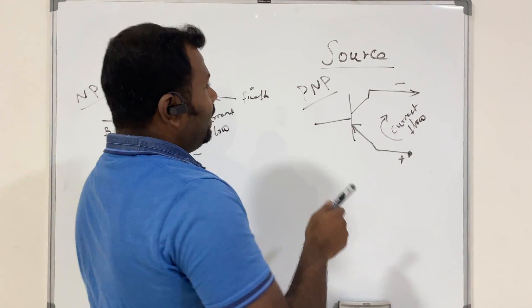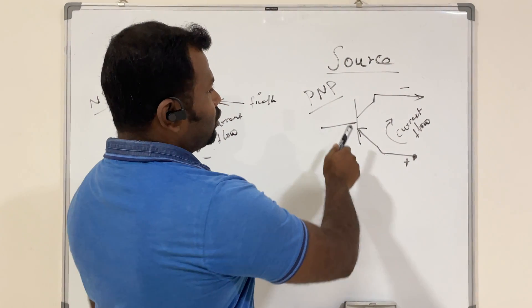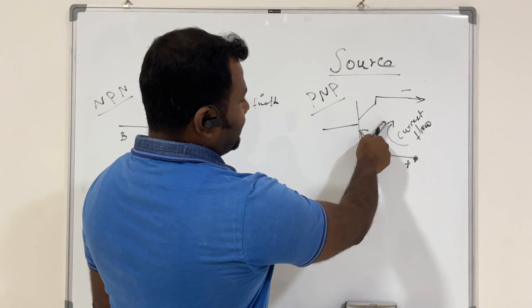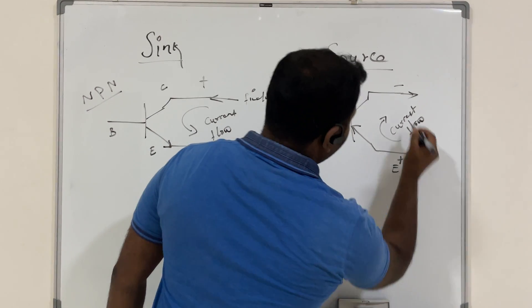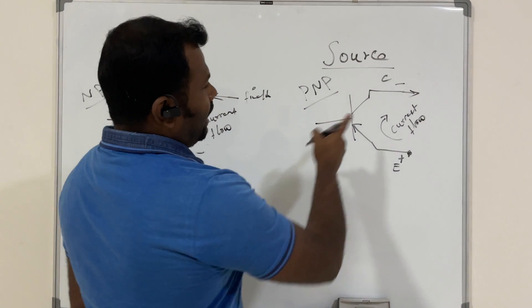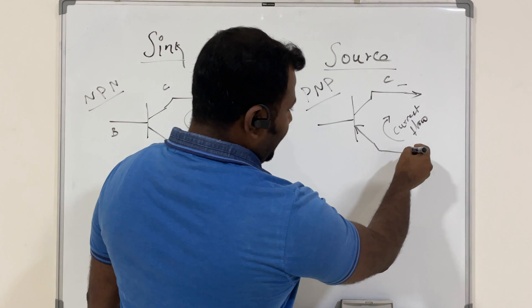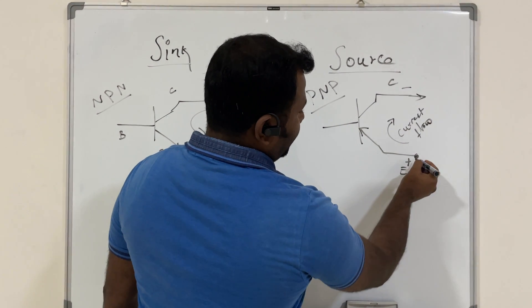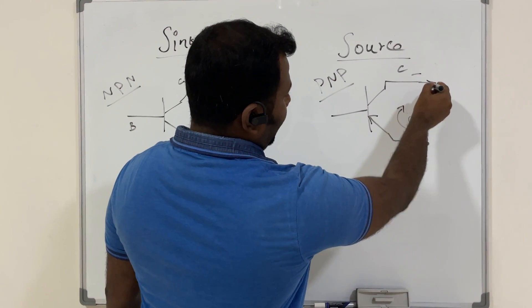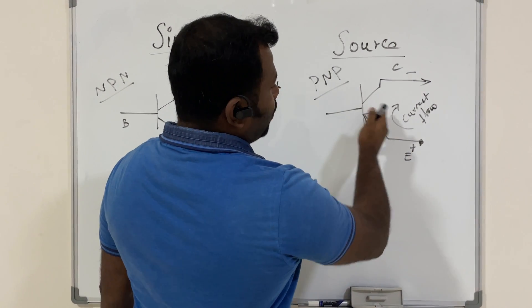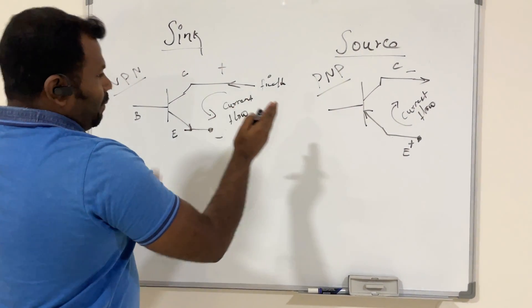In the source type, the I/O card is designed with a PNP transistor. In the PNP transistor, the positive side is connected with the emitter and the negative is connected with the collector. The current flows from PLC to field — from the positive emitter to the negative collector — so the PLC is sourcing the current to the field.